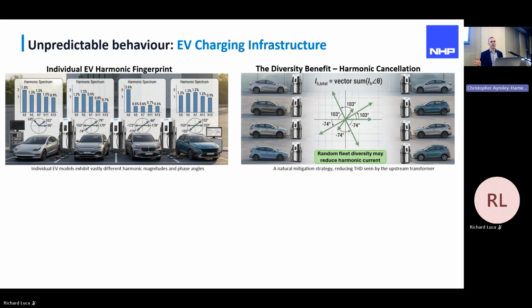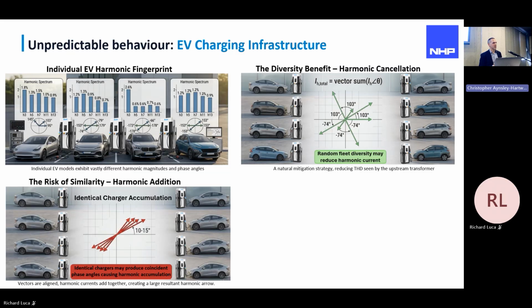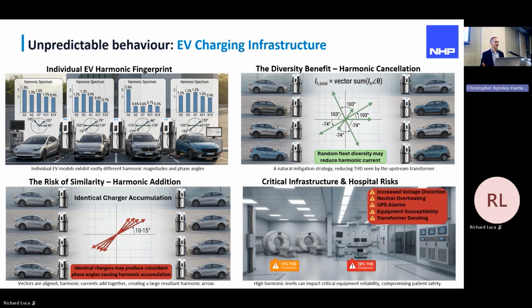So for your facility, if you're looking at some sort of fleet, having diversity is good, where you've got a lot of different performance coming from the OBC. The phase angles are cancelling out to neutralize the harmonics. But where it's not so good, if you're driving a Tesla and you're all plugging in your Teslas at the same time, the vectors are quite similar, which means they add to the network. And that's a problem for critical infrastructure because it's adding something that we haven't accounted for.